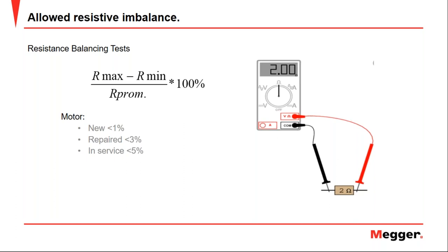Now, what are the maximum values for the resistive unbalance in an electric motor? According to IEEE 1415, if the motor is brand new, we shouldn't have more than 1% of resistive imbalance. If the motor is repaired and coming from the repair shop, the limit is 3%. And if we are talking about a motor in use, the limit is up to 5%. The important thing here is to be able to build trends with different measurements so we can anticipate the catastrophic failure.